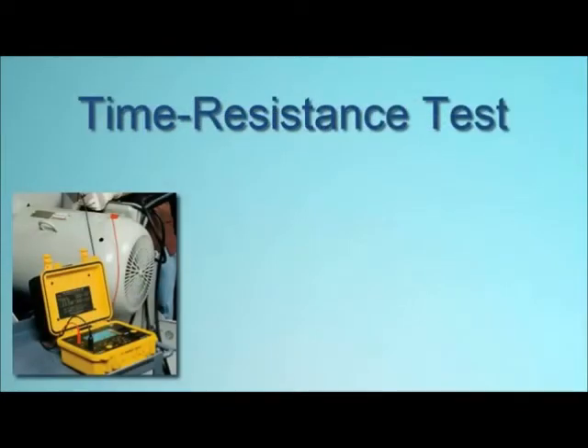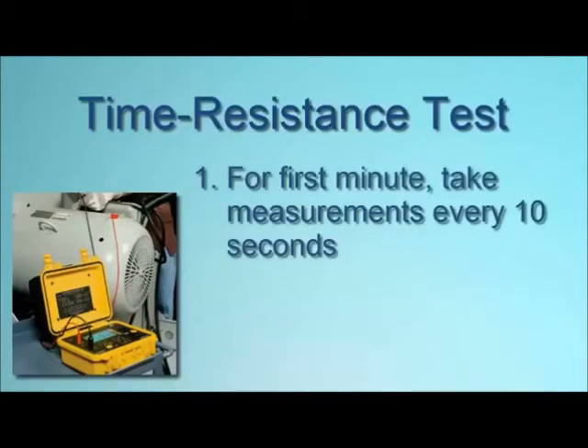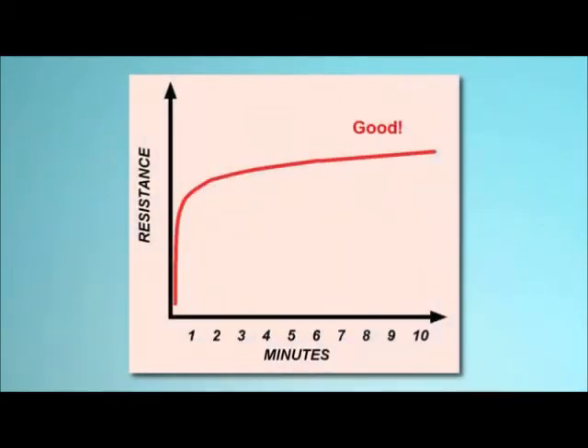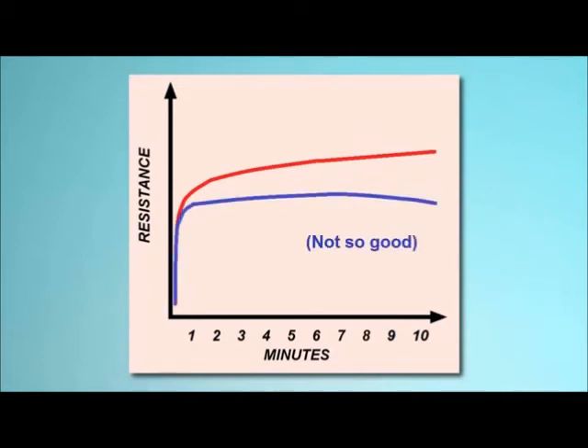Another insulation resistance measurement method is the time resistance test, also referred to as the dielectric absorption test. It involves conducting a 10-minute test. For the first minute, during which absorption current will have the highest effect on resistance, measurements are taken every 10 seconds. After the first minute, measurements are taken once per minute. When you plot the results, you should see a curve that rises relatively rapidly at first and then continues to gradually rise throughout the testing period. If instead the curve is relatively flat or begins to turn down as the test progresses, moisture, dirt, or other factors may be compromising your insulation.